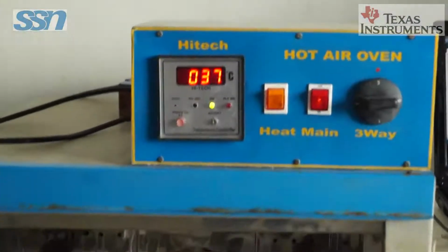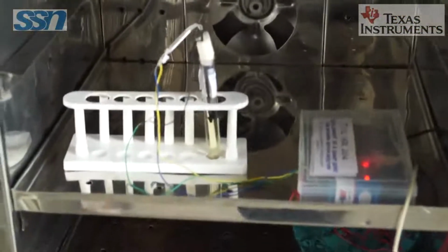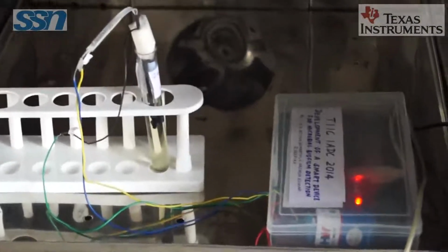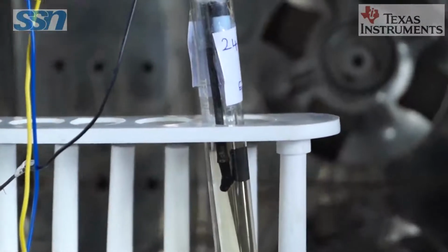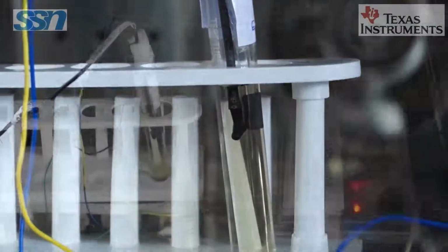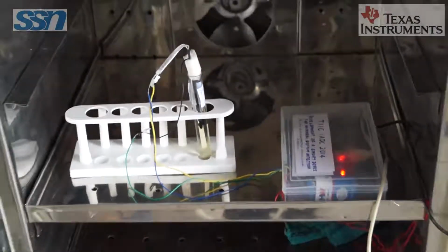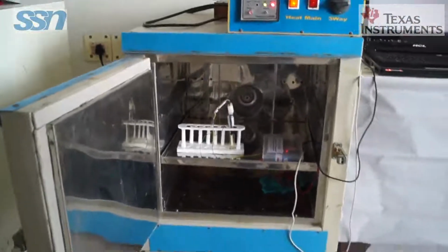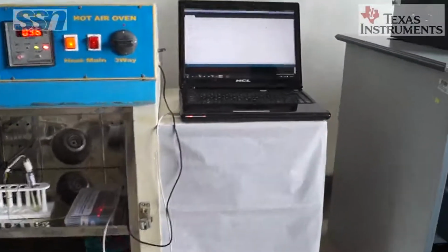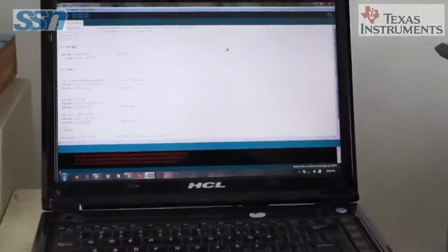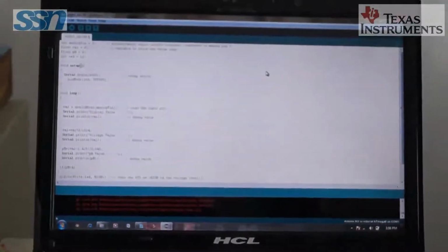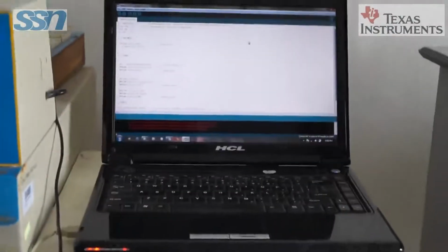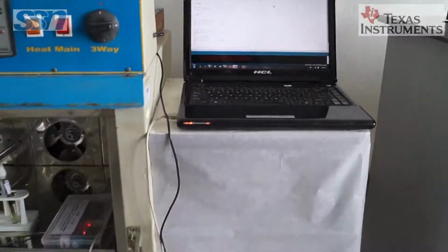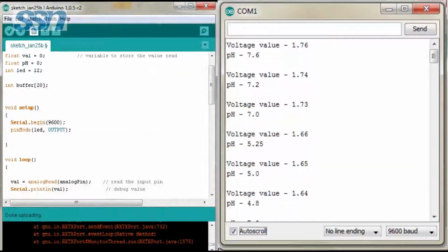The experimentation starts by placing the sensor inside the inoculum, and the whole setup is kept inside the incubator at 37 degrees Celsius. The tip of the sensor and the glass electrode touch the inoculum surface. The setup is interfaced with the system to collect the data, which can be monitored every 2 hours in a serial monitor. The data is also saved in an Excel file using PLX-DAQ software, and the graph is plotted using SimPlot. This is the code along with the data values obtained at an interval of every 2 hours.